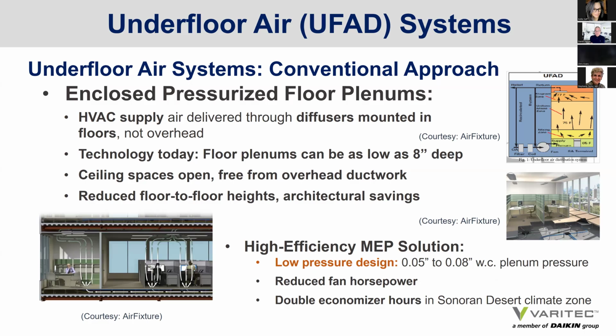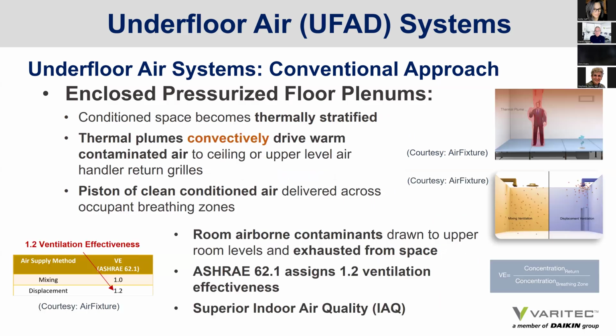So mechanically, using an underfloor or plenum floor solution in a UFAD design might come across as immediately more expensive. There are other architectural savings to be had that can bring about parity, possibly, in the overall first cost if a more holistic approach is adopted for doing the actual financial budgeting of these systems. Again, underfloor is very energy efficient. Plenums are being designed to 0.05, 0.08 inches of plenum pressure, resulting in reduced fan horsepower, and because airflow is at 65 degrees, we can actually increase economizer hours, certainly in areas of dry geographical climate zones.